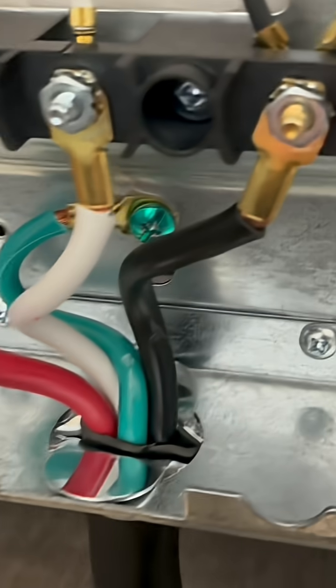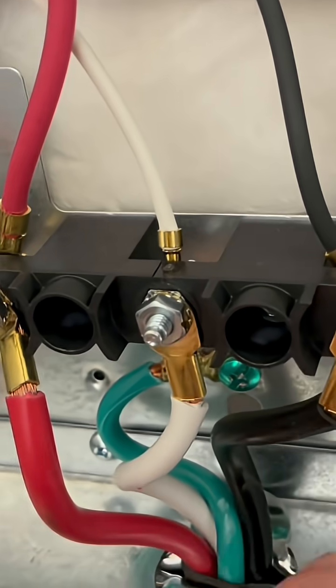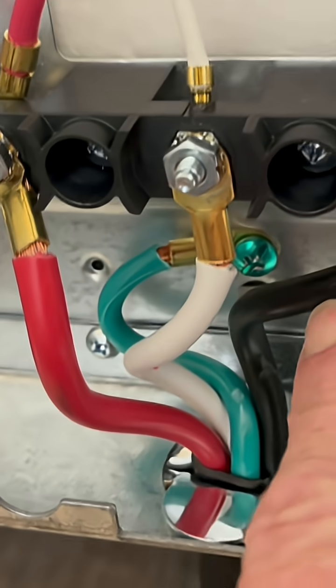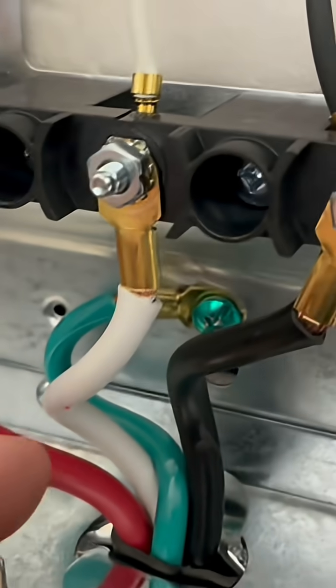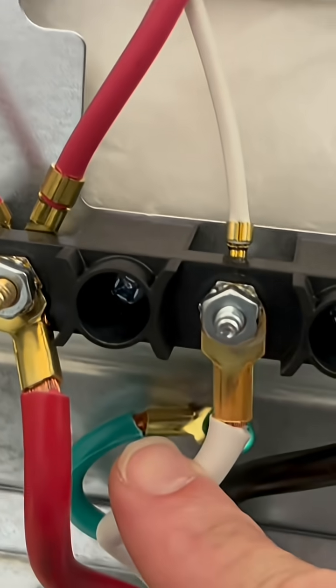Okay, this oven came with a four-prong plug, so I got red, white, black, and green. White's neutral, you got hot and hot and ground. What I need to do here is create a jumper from the white to the ground.